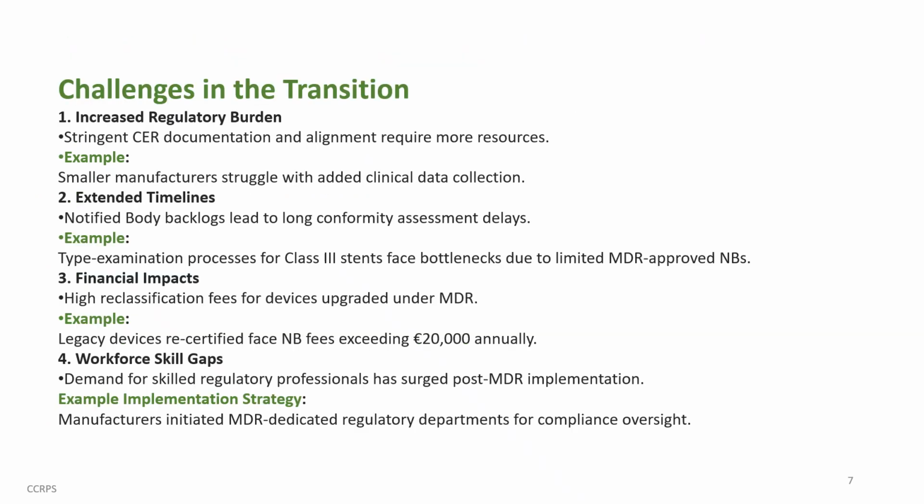Challenges in the transition. Increased regulatory burden: stringent CER documentation and alignment requires more resources. For example, smaller manufacturers struggle with added clinical data collection. Extended timelines: notified body backlogs lead to long conformity assessment delays. Example: type examination processes for Class 3 stents face bottlenecks due to limited MDR-approved NBs.